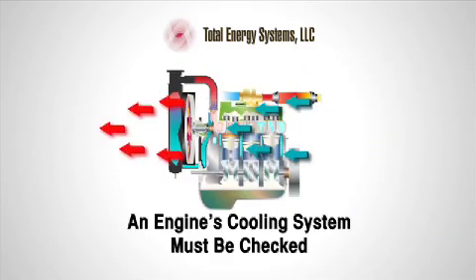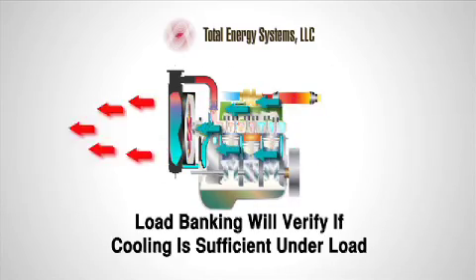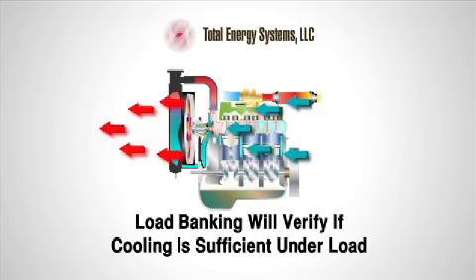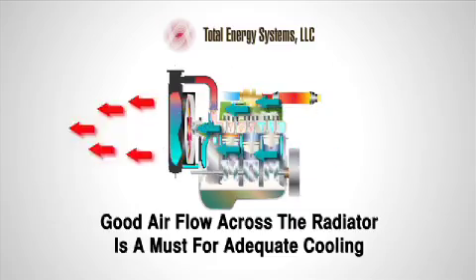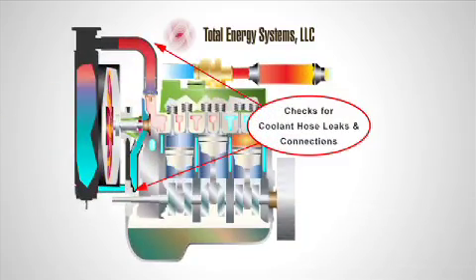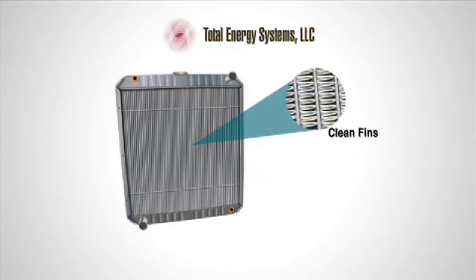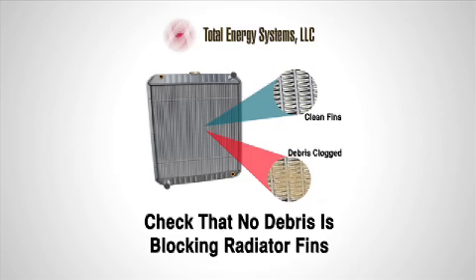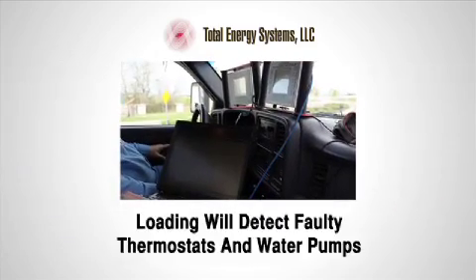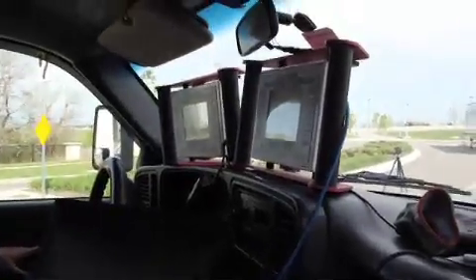Another cause of underperformance is problems with an engine's cooling system. Load banking will verify if cooling is adequate for the generator to carry the load without overheating. Airflow over the radiator is critical for cooling. Most common problems with cooling are loss of coolant due to radiator leaks and faulty hoses. Also, radiator fins can become blocked with debris, which will significantly reduce airflow and the radiator's cooling capability. Within the engine, cooling issues such as a faulty water pump or faulty thermostat will be identified if insufficient cooling is detected during a load bank test.